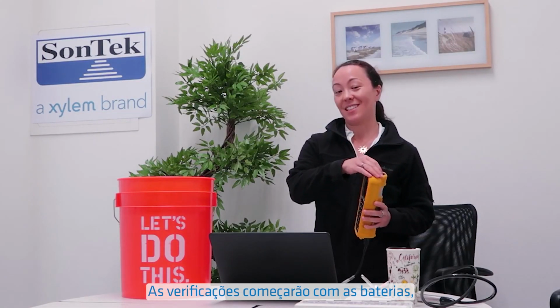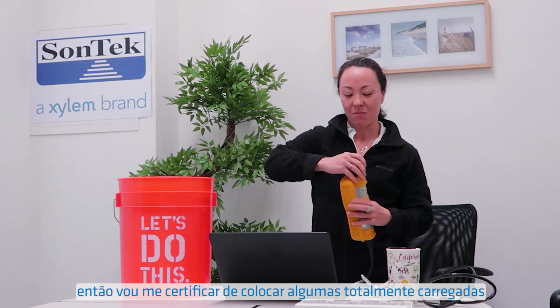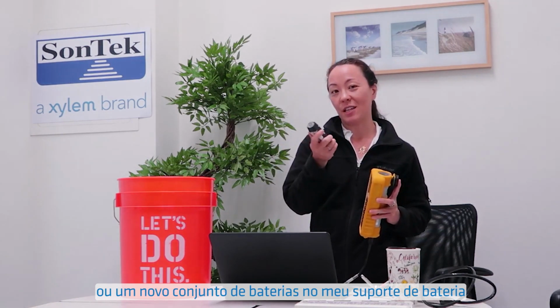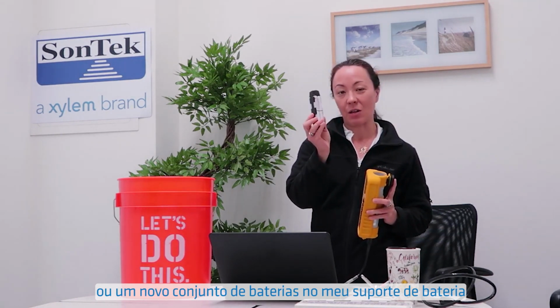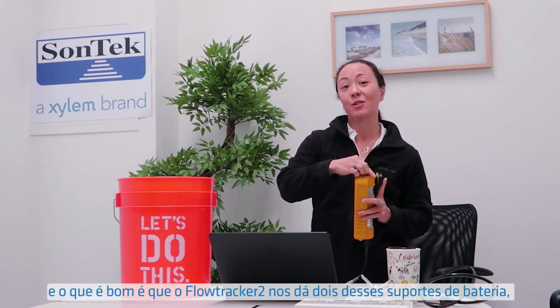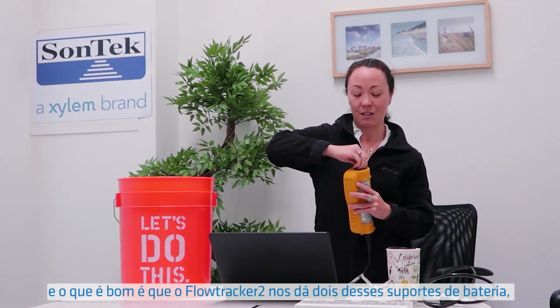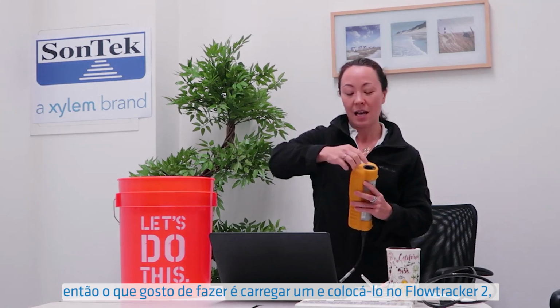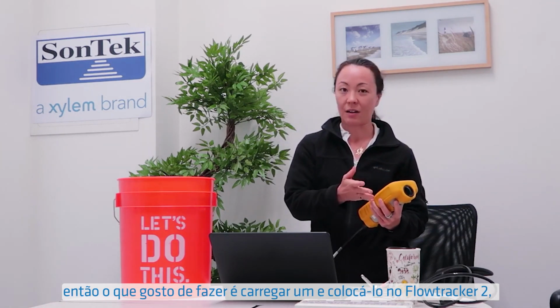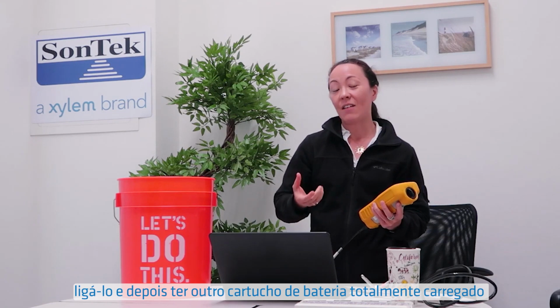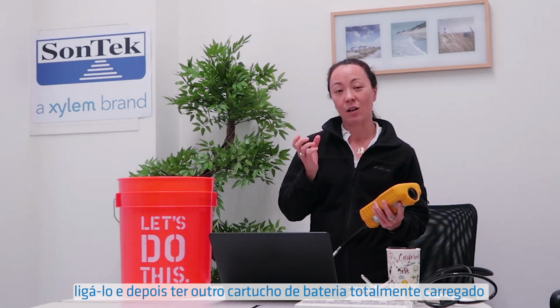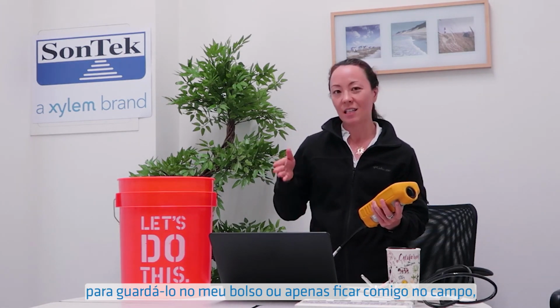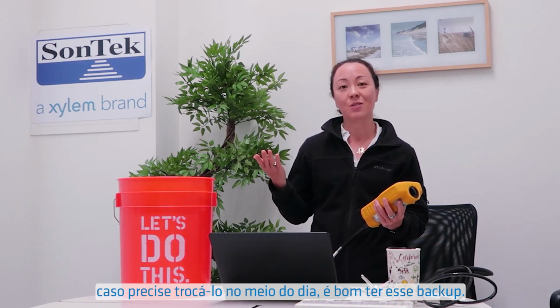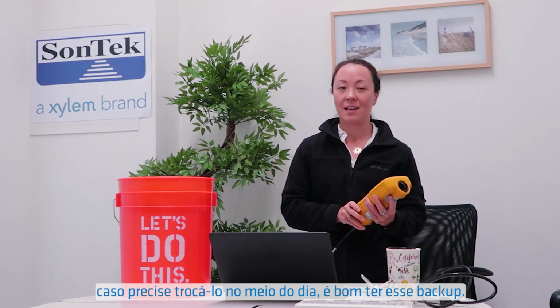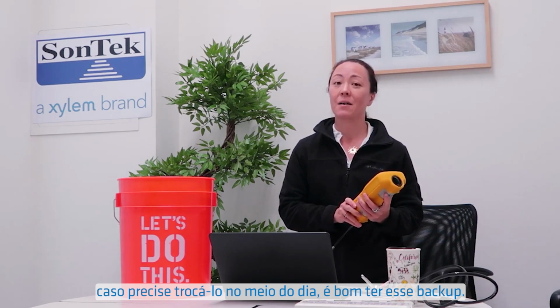Our in-office checks are going to begin with the batteries. So I'm going to make sure I put some fully charged or a fresh set of batteries in my battery holder. And what's nice is that the FlowTracker2 gives us 2 of these battery holders. So what I like to do is load one up and put it in the FlowTracker, turn it on, and then have another fully loaded battery cartridge to keep in my pocket or just keep with me in the field in case you need to hot swap it in the middle of your day. It's just nice to have that backup.